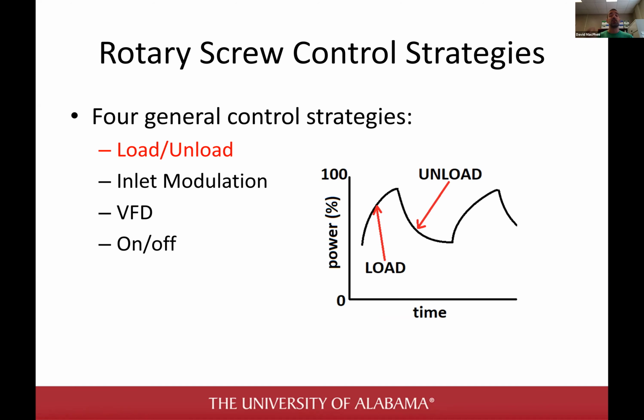Let's say you are monitoring the current going into this compressor, and you've exported that to an Excel spreadsheet, and figured out the power in watts or kilowatts over time. This is kind of what it would look like if you were in a load-unload control strategy. When you buy a compressor, it comes with one or two control strategies you can switch between, usually just one. This is what it does to keep pressure in your system so you can use compressed air in your facility: load and unload.